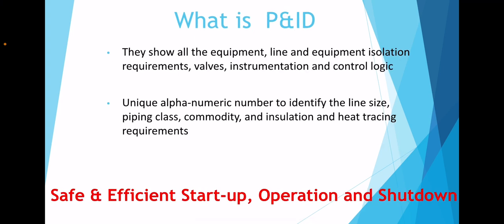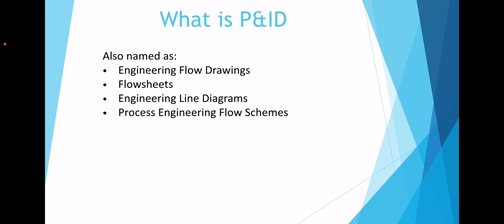P&IDs show all equipment in sequence, lines and equipment isolation requirements, various valves, instrumentation, and control logic associated with the process plant. Line numbers are indicated with a unique alphanumeric number identifying the size of the line, the piping class, the service the pipe sees, and the insulation and heat tracing requirement. P&IDs provide a safe and efficient way to start up, operate, and shut down the plant. They may also be called engineering flow drawings, flow sheets, engineering line diagrams, or process engineering flow schemes by different companies, though the information contained in them is the same.